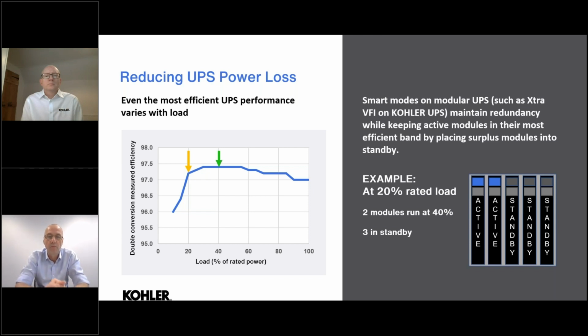So in this example, we've got 20% of the rated load, so we're running 2 modules to give us redundancy. So we're running that at 40%. So that's in the most efficient band for those units. And with this mode, we've still got the 3 others in standby. So if the load increases, we need the capacity, or if we have one taken off for maintenance, for example, the others are there available to come on, keeping everything safe, secure, but also in the most efficient band for what they're designed for.